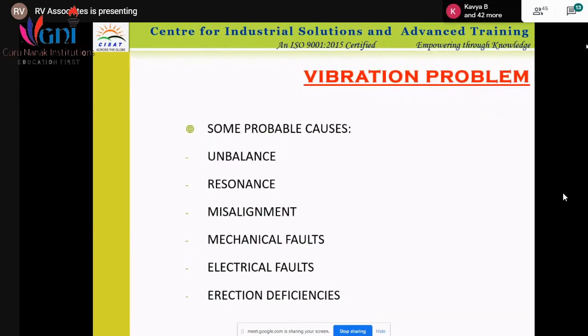Another one is vibrational problems like unbalance in the system. Unbalance comes when there is a coupling, like a motor with a conveyor in between, and you are using a coupling. If that coupling is not proper, it will give unbalance. Unbalanced condition will give you resonance, and that resonance puts pressure on the bearing, and that bearing will fail. So it's like a chain. Once there is a failure, it becomes a failure of the complete system.